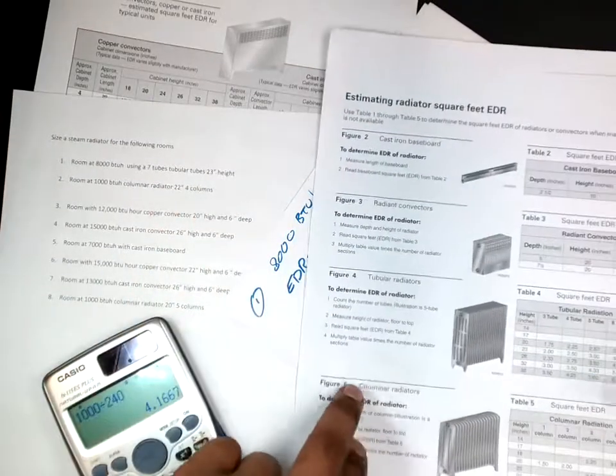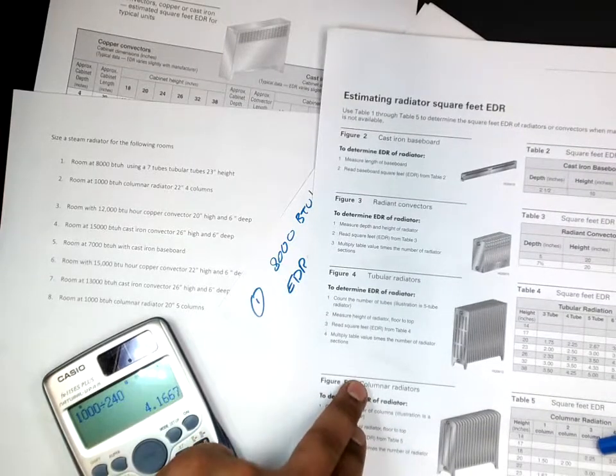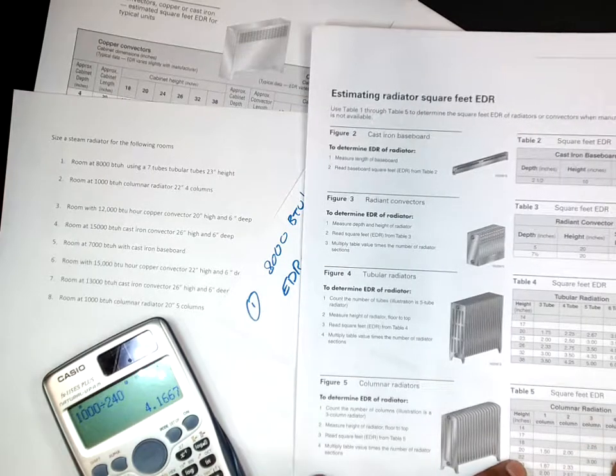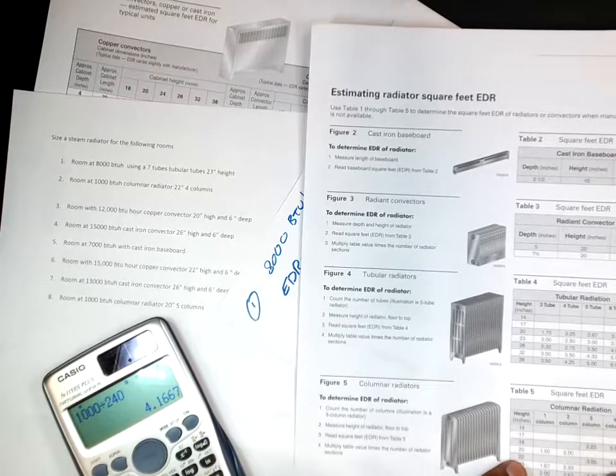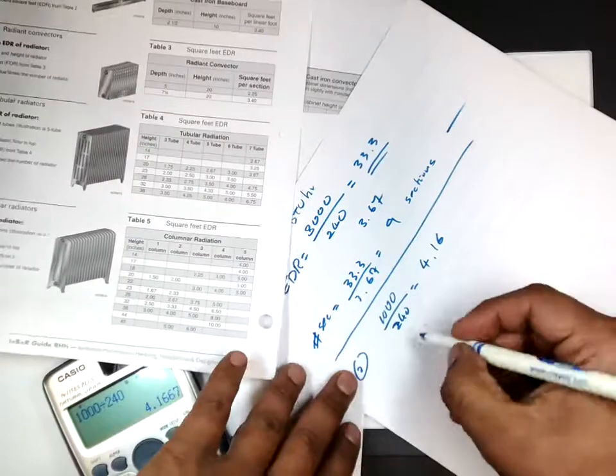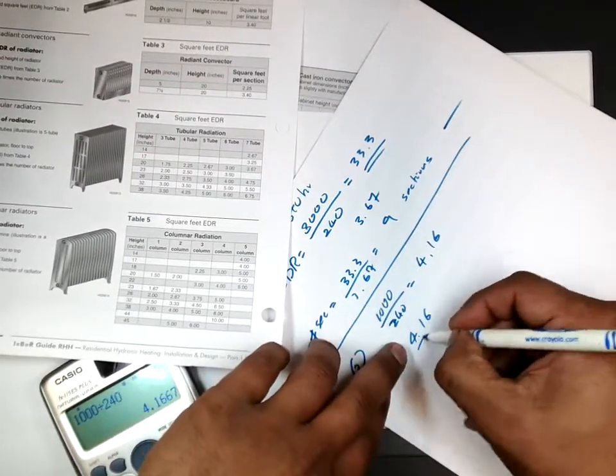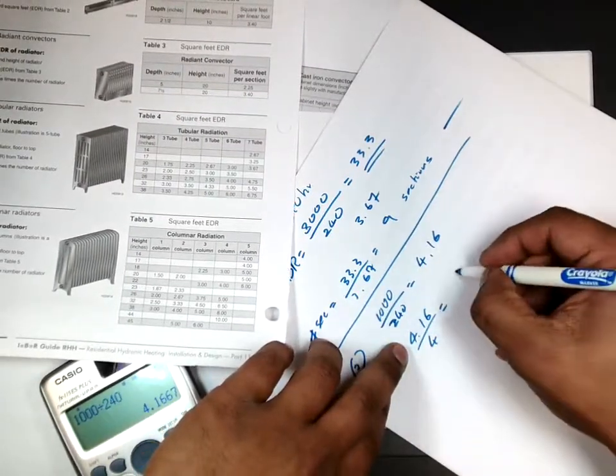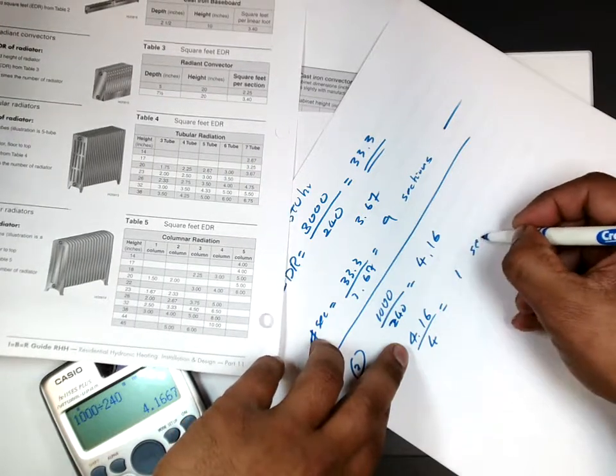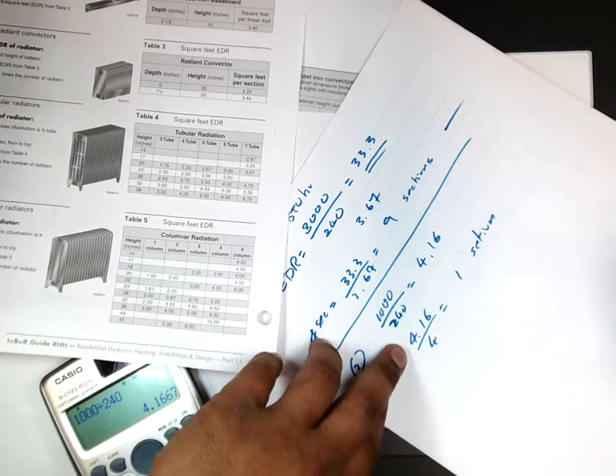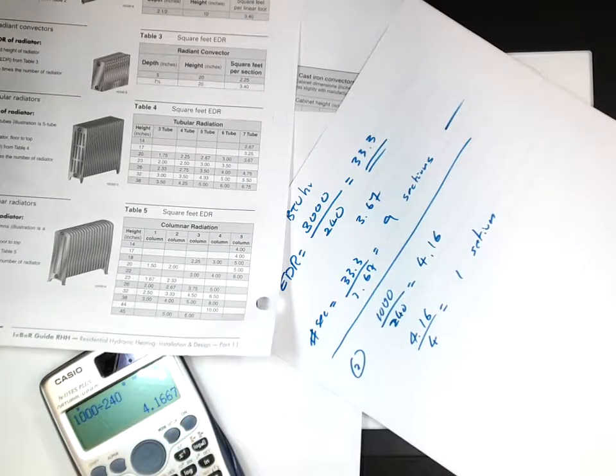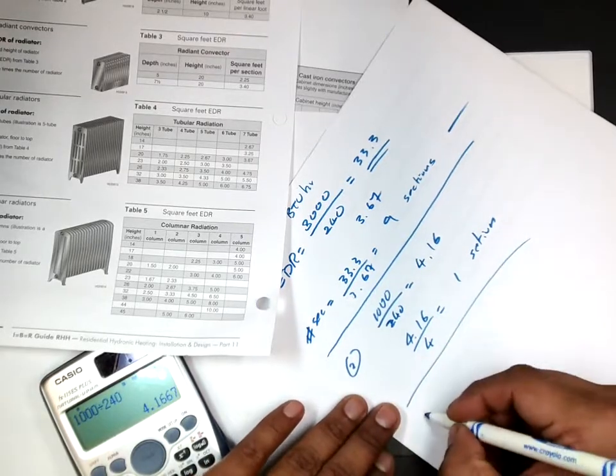Then I'm going to go to columnar radiator, which is this one. And how many? 22 inches. It's here. And how many columns? 4 columns. So it's going to be 4. So 4.16 over 4, and that will be one point something. I'm going to say one section is enough. Let's take a drill and see two sections, but one section you can do. It's a very small area, so it's good to have only one section in there. Number two. Number three.